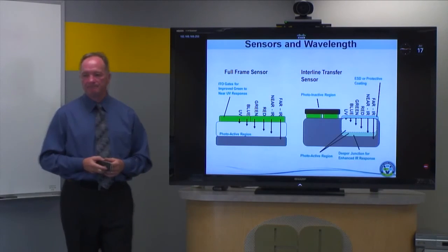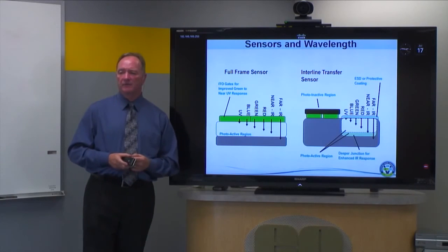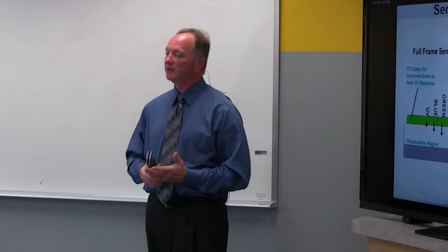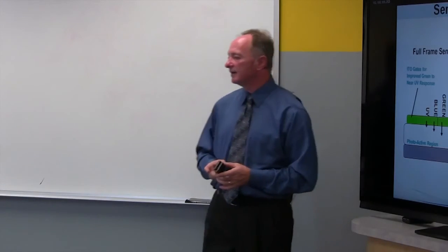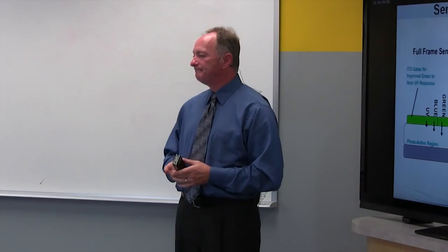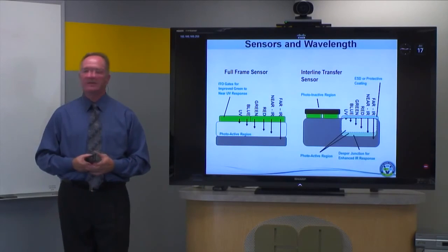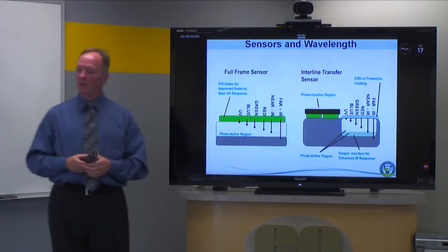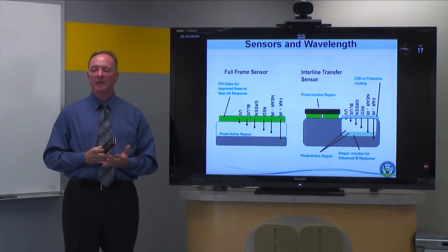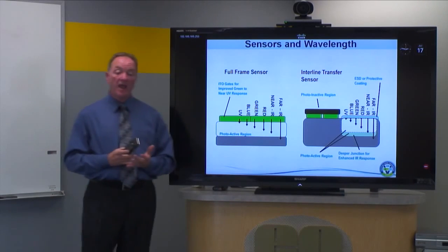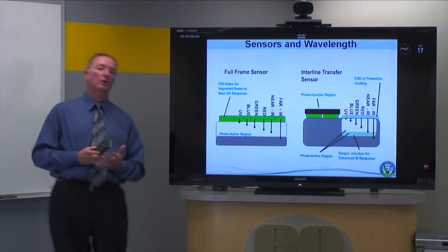On sensors and wavelength — there are a lot of changes that have happened over the years. Full frame sensors have gotten much better, adding thin films to collect short wavelength light. Interline transfer sensors have gotten deeper junctions so they can collect near IR better. Sometimes if you need to optimize sensitivity, it depends on the sample and what camera you have — but it's worth understanding that some sensors are designed specifically to collect far IR or short wavelength light better.